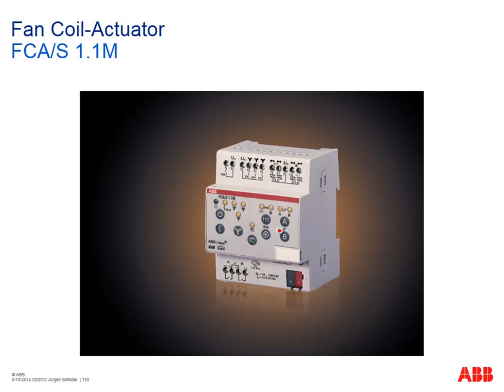And now I continue with the fan Coil-Actuator FCA/S 1.1M. M means here manual operation. You can see we have here our standard manual operation principle. By pressing long this button here, the fan Coil-Actuator goes inside the manual operation mode, and by pressing this button we can test our fan coil unit and change the speed of the fan, or open here for example the valve for heating, the valve for cooling, or we can simulate here the binary inputs.